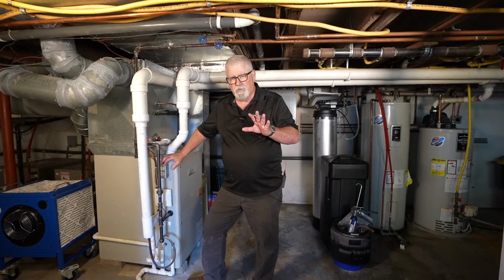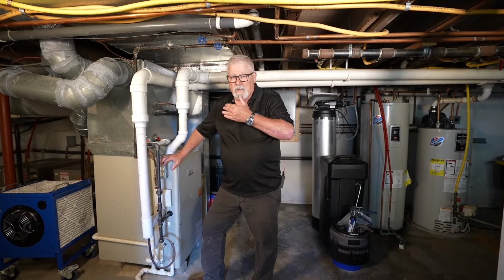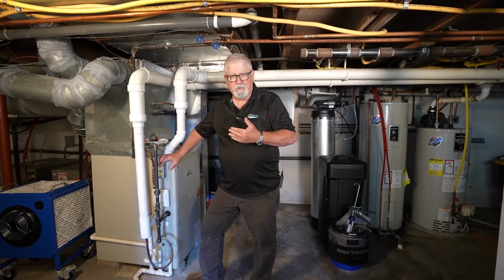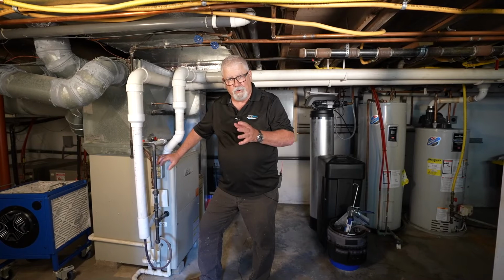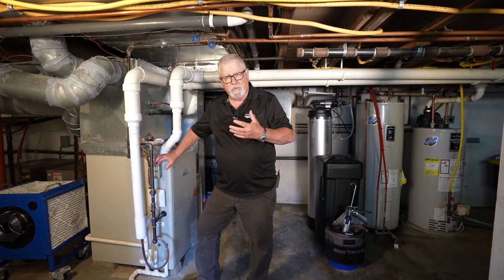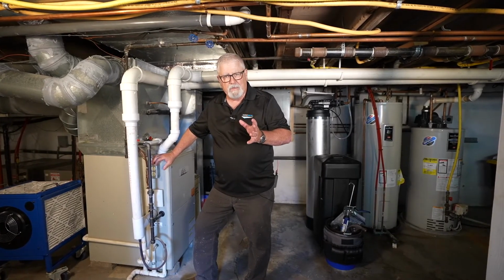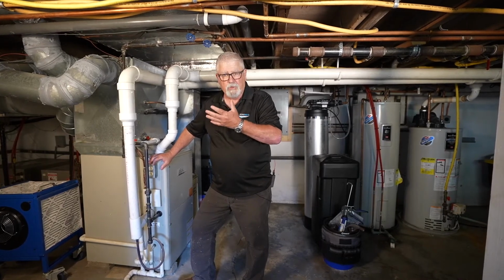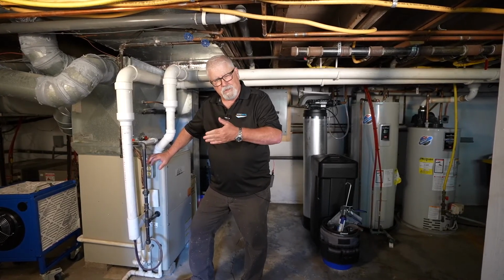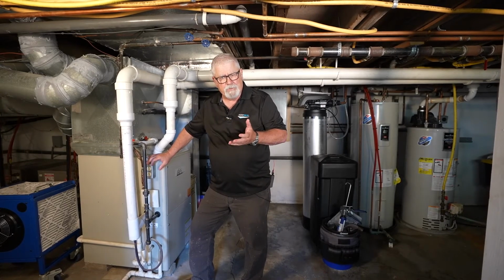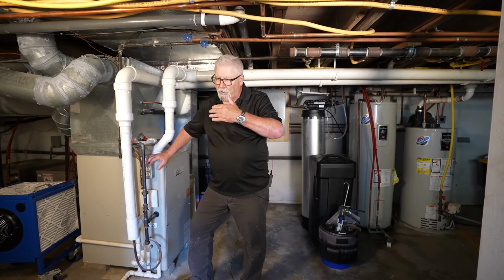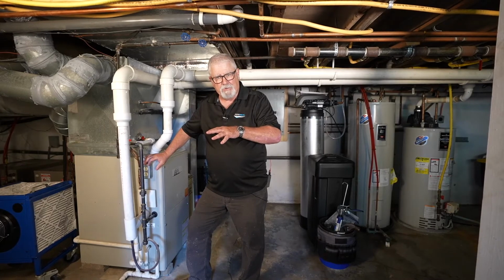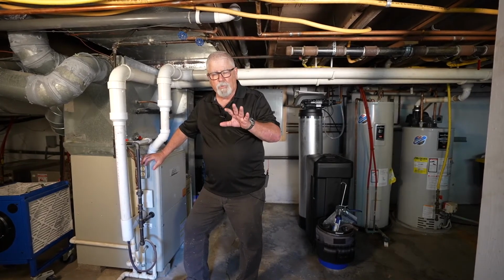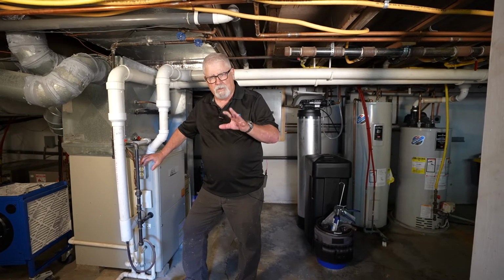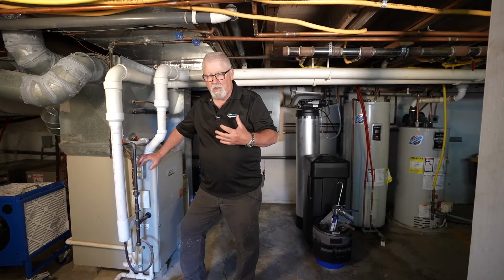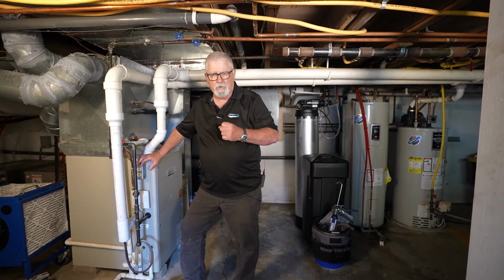Now, the one thing we are going to do to finish this job up, though, I stopped all of the supply duct leakage down here in the basement. I've still got a little bit of return, so I'm putting the basement under a small little negative pressure. So all we're going to do to take care of that is we're just going to cut a grill in the door to the upstairs. It's kind of off to the side so people don't mind putting the grill in there. By adding that grill, we're going to eliminate that negative pressure down here in the basement, and everything will be good. So we're real happy on this one. We did a great seal. Customer is going to be very satisfied. It's going to be a lot more comfortable upstairs, and overall, a great job.